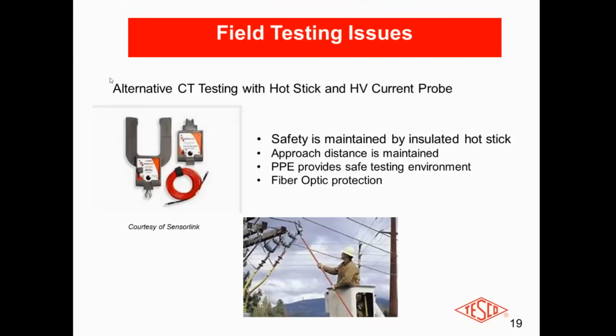So it's basically doing the same thing as a type of Rogowski coil, but it's doing it from a distance, and that could be a 25, 30-foot hot stick. And what they're doing is they're opening up a cabinet, even if it's on ground level, and they're using the appropriate hot stick to go into the cabinet and make a single phase measurement, remove it, pull it back out again, put it back in, do phase B, and do the same with phase C. Now you can do 3 tests and you get the same results. So it's a bit more practical. It's certainly more approachable to do it that way. The high voltage probes, I would argue, are not quite as accurate as the Rogowski probes, but if you're getting a decent ratio measurement and you're comfortable with the results, you've achieved what you set out to do, which is to do a CT ratio check on that service.